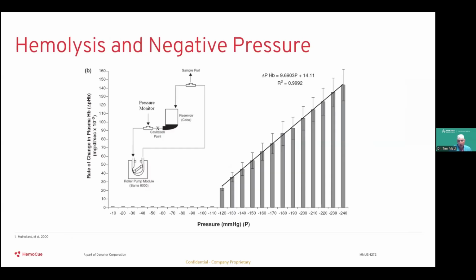And there was also an interesting study in 2000 from Mulholland et al. that showed that when you applied a negative pressure to a cardiotomy reservoir, either for bypass or for cell saver, there becomes a threshold after which you get a linear increase in the rate of free hemoglobin release in the cells that are exposed to that system. Starting at about negative 120 millimeters of mercury, you get this nice linear increase in hemolysis because of the mechanical damaging effects of the vacuum that's been applied to the system. So this is one of the reasons why, when we choose cannulas and set our vacuum sources for cell salvage, we try to keep negative pressures no more negative than about 100 millimeters of mercury in our systems.